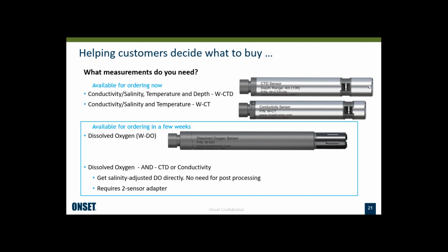And the one question that came up earlier today was, can I combine 2 of the same types of sensors? In other words, can I have CTD sensors at 2 different depths? And you could do that. With the splitter, you have the cable run down to the first depth, have the splitter at that depth, and have a cable running down to the sensor at the lower depth. So you can do things like that. There's a lot of creativity in terms of how these can be configured. We'll probably come out with some sort of application note showing some examples and helping people configure cables and splitters and sensors.